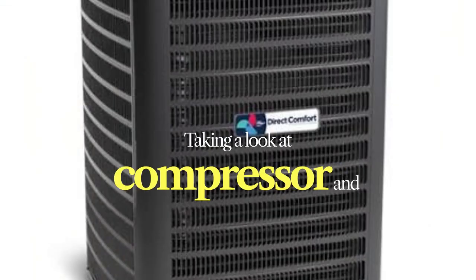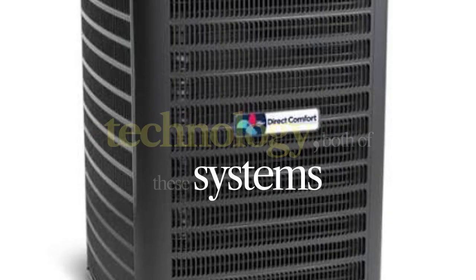Taking a look at compressor and fan technology, both of these systems are basic single-speed models. A single-speed setup means the compressor and outdoor fan turn on at 100% capacity whenever there is a call for heating or cooling and run until the thermostat is satisfied.